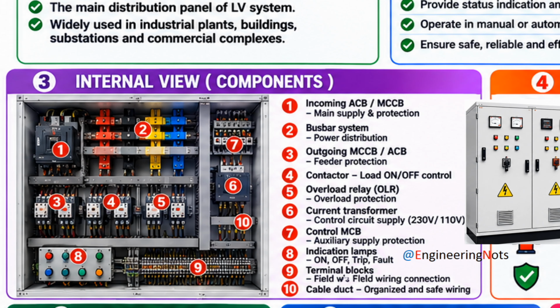Now, let's open the PCC and see what's inside. At first glance, it may look like a large metal cabinet. But inside, every component has a specific purpose. Let's start from the top. This is the air circuit breaker, or ACB. It is the main incoming breaker of the panel. Its job is to protect the entire low-voltage system against overloads and short circuits. When a serious fault occurs, the air circuit breaker disconnects the incoming power to prevent damage to equipment.